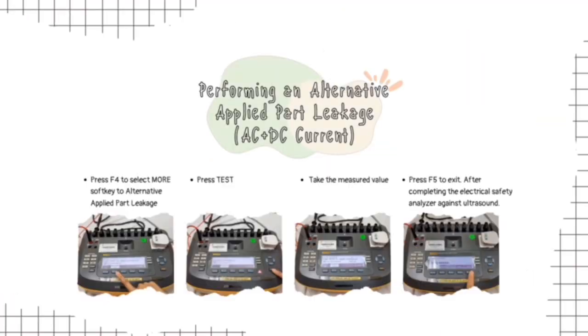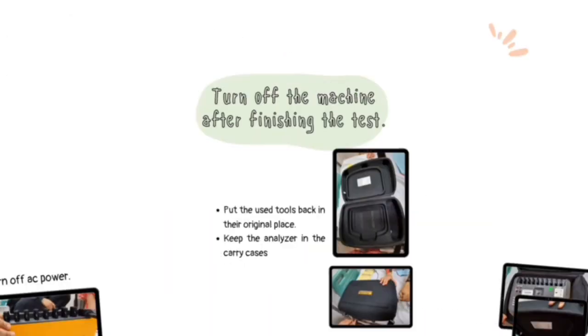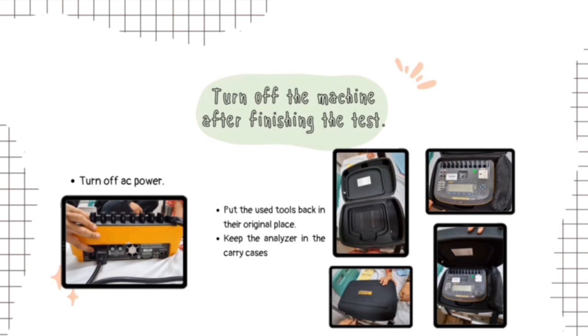Before we go to the end, we must check the performing an alternative applied part leakage AC plus DC current. First, press F4 to select the more soft key, then alternative applied part leakage, and then press test. Take the measured value and then press F5 to exit after completing the electrical safety analyzer test on the ultrasound. Lastly, we must turn off the machine after finishing the test.